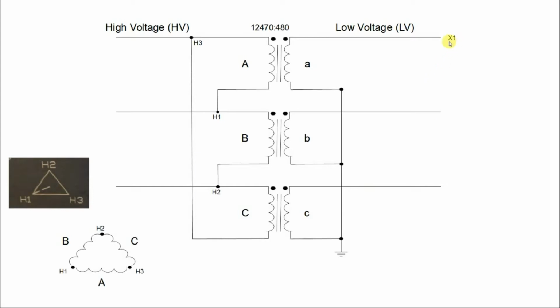I am going to denote the ends of my lines with X1, X2, and X3. This is a little difficult to see in the Y configuration, so X0 I have for my ground down here. Here is my Y connection showing the exact same configuration. X1 to X2 comprises A and B phase, X2 to X3 comprises B and C phase, and they're connected in Y. This dotted line denotes that it is grounded, and they are labeling the ground X0, which I have shown here.